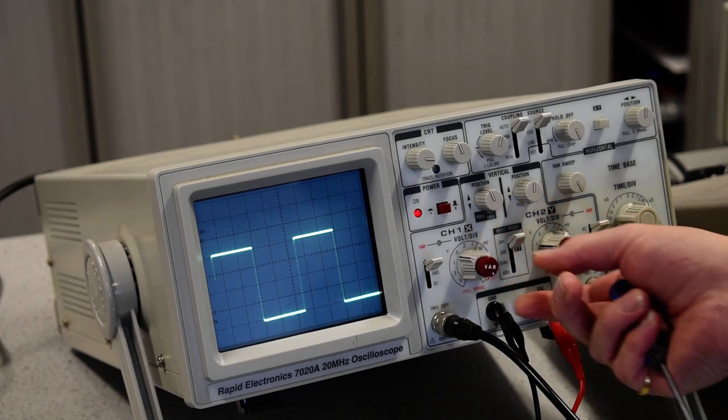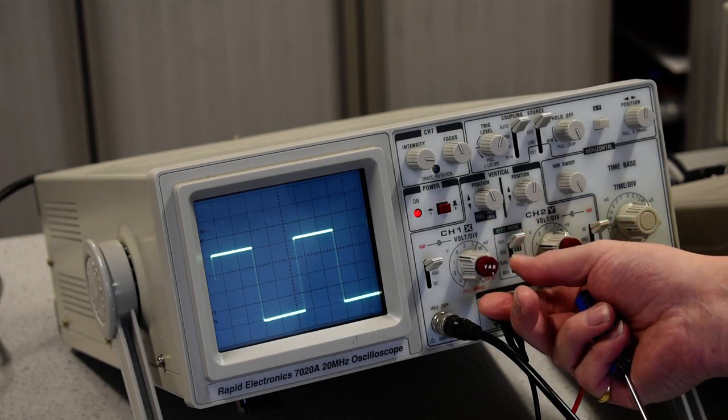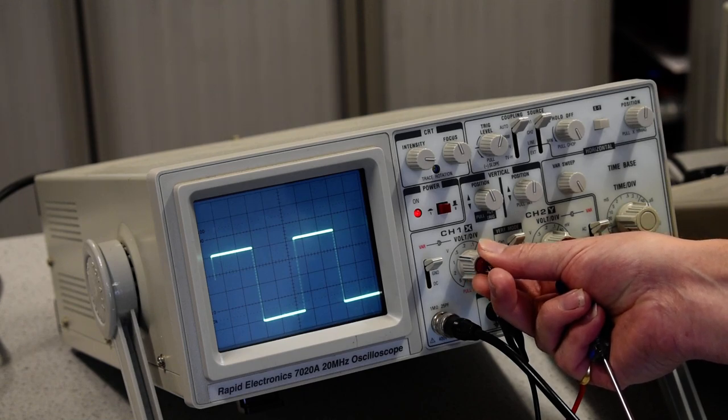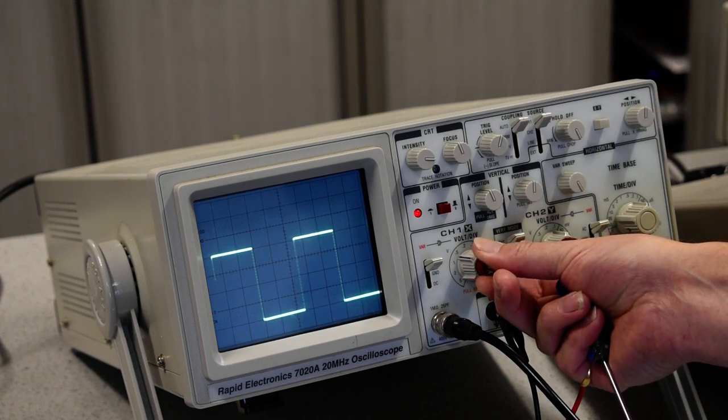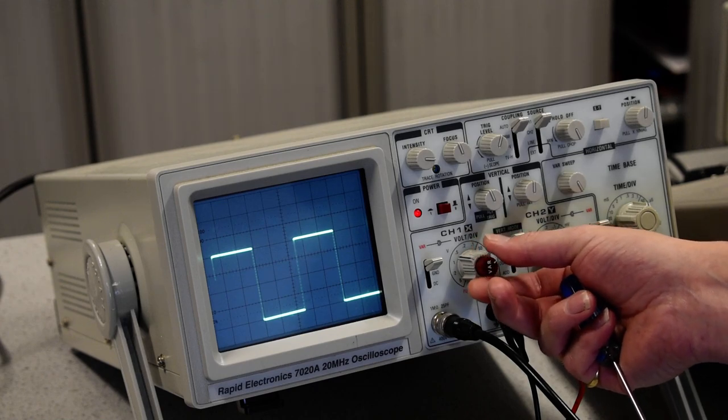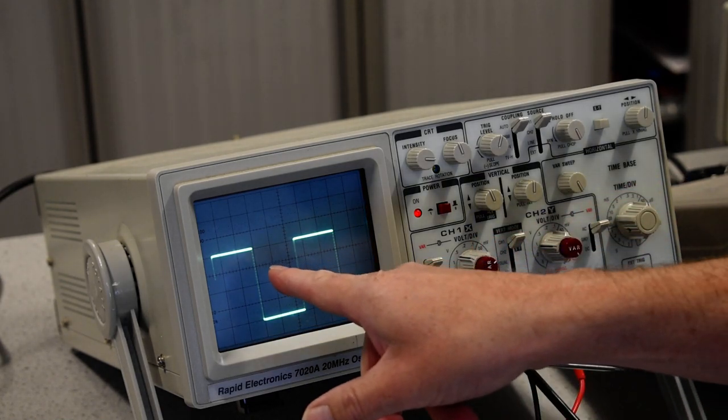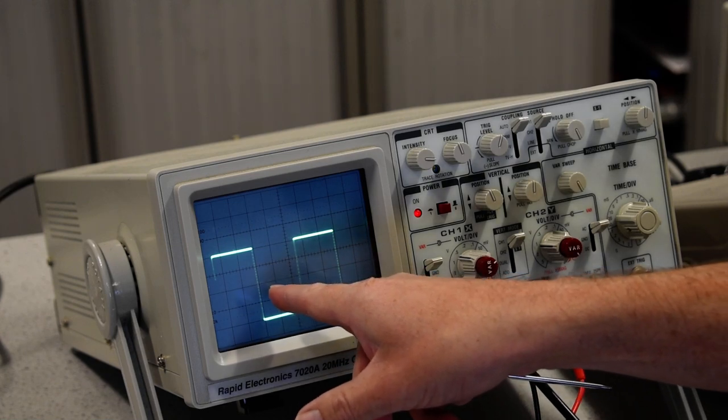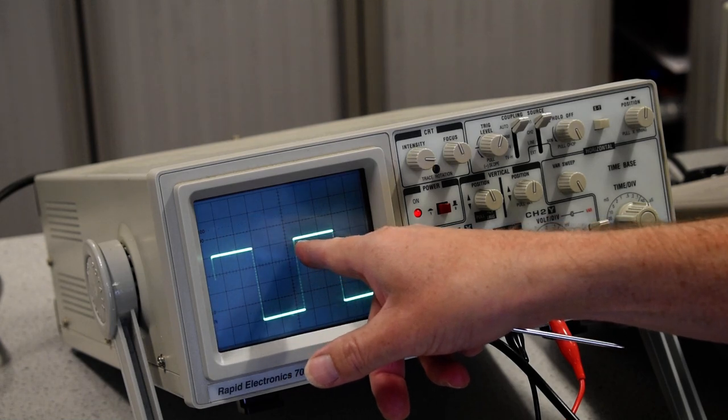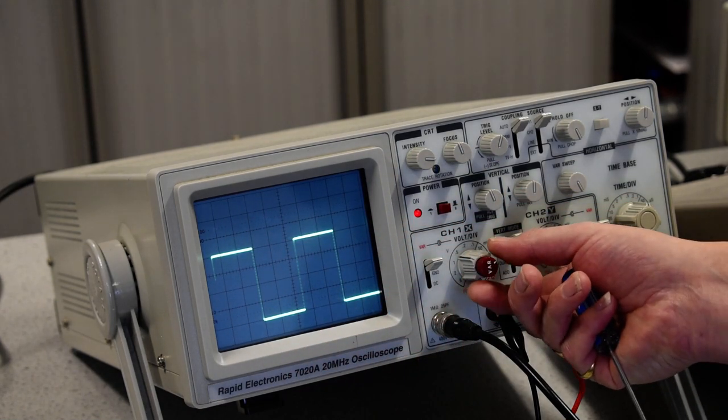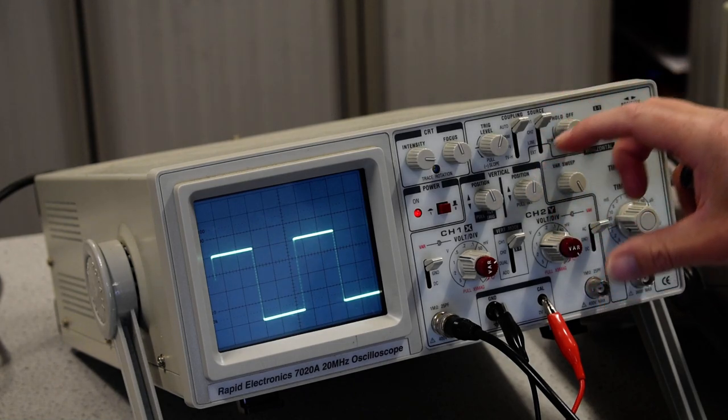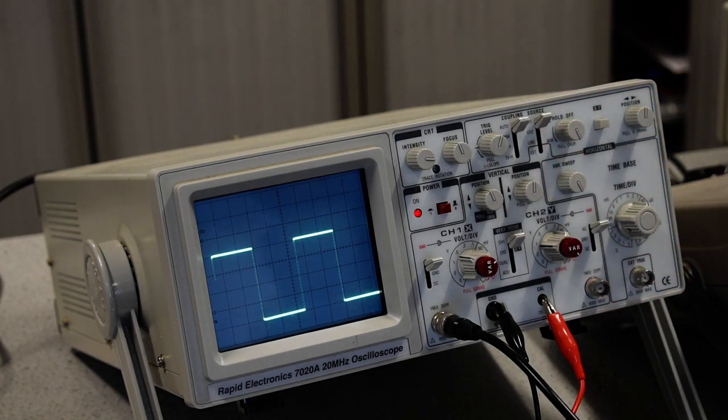So we're on 0.5 volts per division. We can use the VAR dial to tweak the screen such that we've now got accurately 0.5, 1, 1.5, and right on that grid line 2.0. And we just leave that VAR setting there now because we have properly calibrated the oscilloscope.